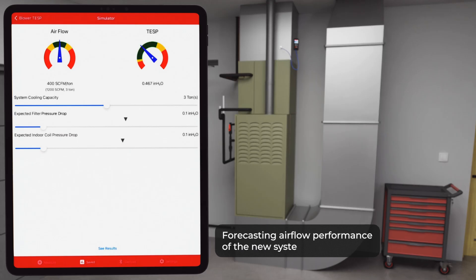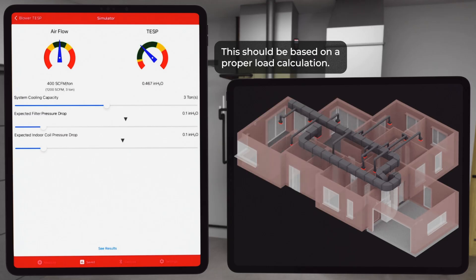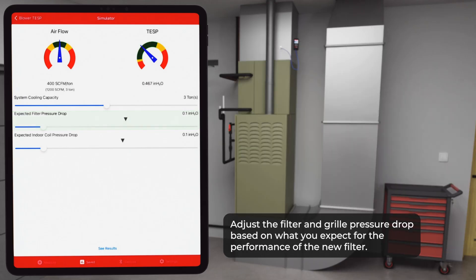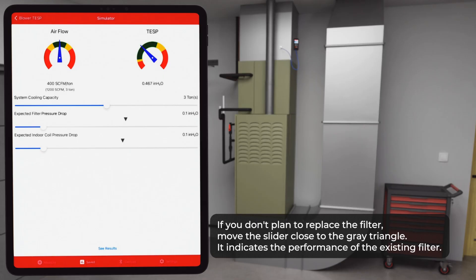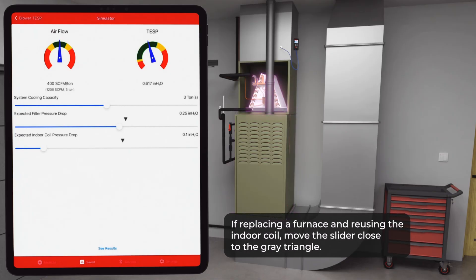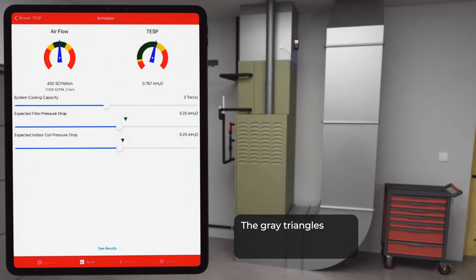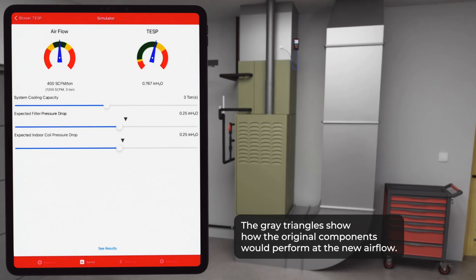Now it's time to forecast the airflow performance of the new system. Start by adjusting the capacity slider — this should be based on a proper load calculation. Next, adjust the filter and grill pressure drop based on what you expect for the performance of the new filter. If you don't plan to replace the filter, move the slider close to the gray triangle, because that indicates the performance of the existing filter. Finally, adjust the indoor coil pressure drop based on the manufacturer's literature at the correct airflow for the new system. If you're just replacing a furnace and plan to reuse the indoor coil, move the slider close to the gray triangle, because that indicates the performance of the existing indoor coil. The gray triangles show how the original components would perform at the new airflow — a great visual to see if a coil or filter upgrade is necessary.